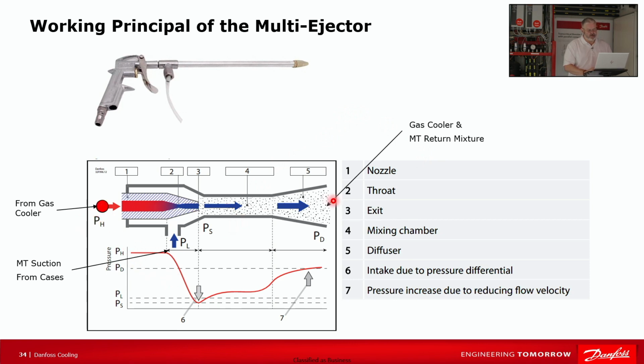So if we travel through the ejector again, we go from the gas cooler inlet. That's our high pressure water going into the wand of the pressure washer. So we're to that point on the pressure washer wand. Then we bring in the medium temp suction from the cases, which we haven't explained yet, but we're going to. Just trust me for the moment.